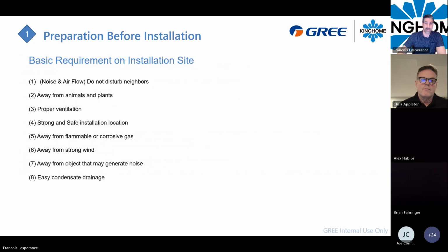When you're on site, it's really important to check where you will install the unit. You will need proper ventilation around the unit. We will talk about all the requirements around the unit. Make sure you are not too close to the neighbor, and away from plants and animals or anything that can block the outside coil. Stay away also from strong winds. Most of the time, strong winds may generate some issues with any kind of heat pump. If the unit always has strong winds going through the condenser coil, that may cause some problems to the unit.